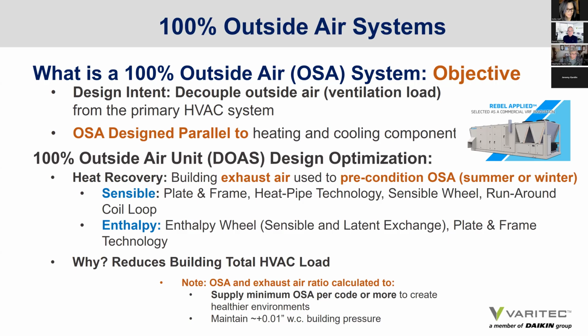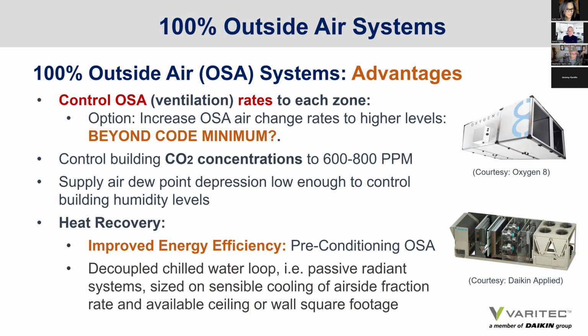So in looking at DOAS units, we want to have the right balance between outside air versus exhaust air. A couple of advantages outside of reduced outside air load on a MEP system is you can now inject, in a 100% outside air system, the assigned outside air rate to each zone, because it's always been a challenge in ASHRAE to assume that because we have a mixed air plenum and an air handler, we're getting the appropriate distribution of outside air percentage to the return air percentage distributed uniformly throughout each zone within a building. How do you verify that? Well, it's very difficult, if not impossible, to do.